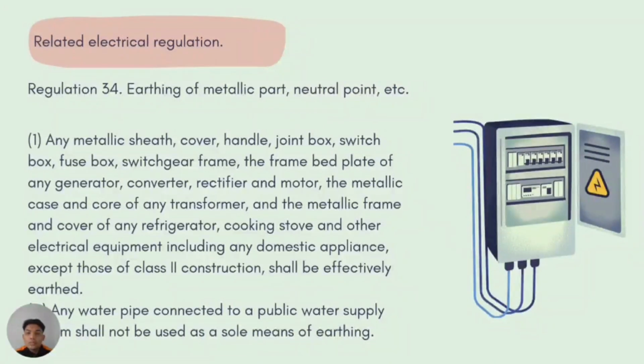This relates to the requirement that the metal clad of the final circuit must be properly earthed, which the wireman did not comply with. Secondly, any water pipe connected to a public water supply system shall not be used as a sole means of earthing. Okay, this directly addresses the issue where the wireman used a water pipe connected to the public supply as earthing, which is not allowed.